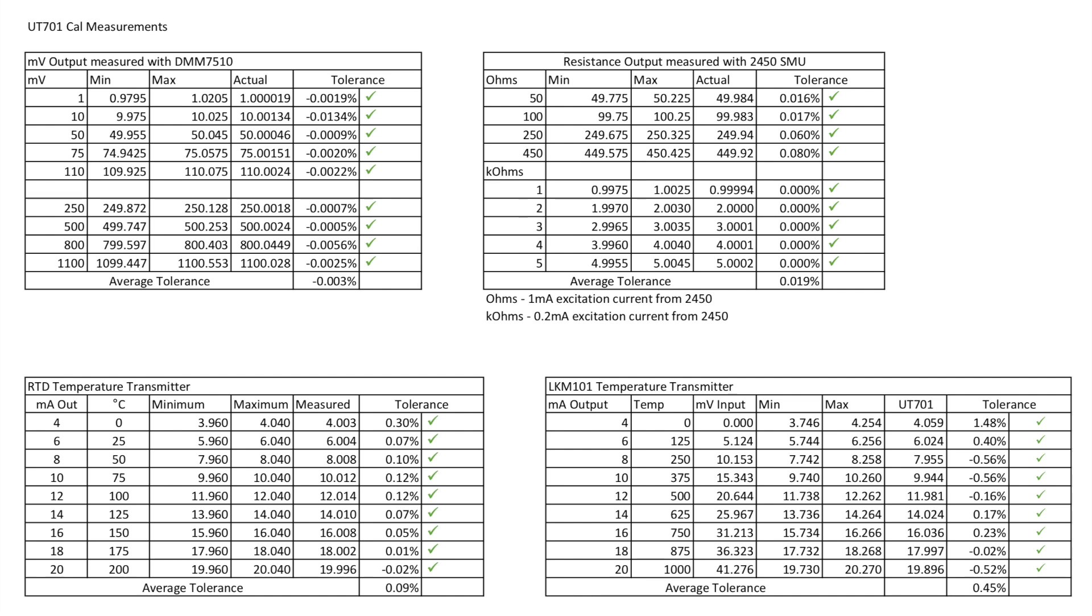On the right hand side, we've got the resistance values measured with the 2450 SMU. It looks like I used slightly different excitation currents than in the video as well, and that will account for some differences. But again, good set of results, especially on the kilo ohms. They are all within spec. So it's worth noting that if the excitation current changes, that can affect the result as well.